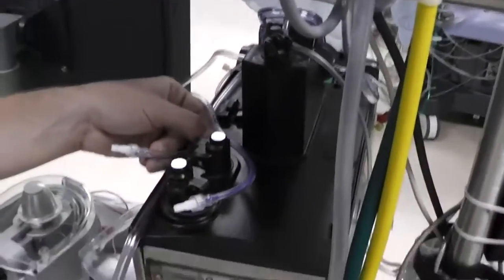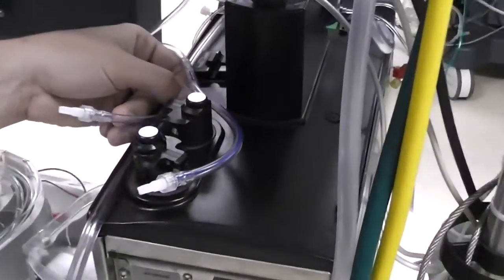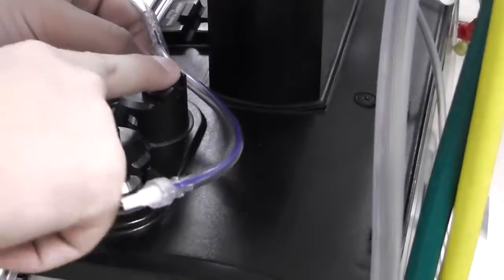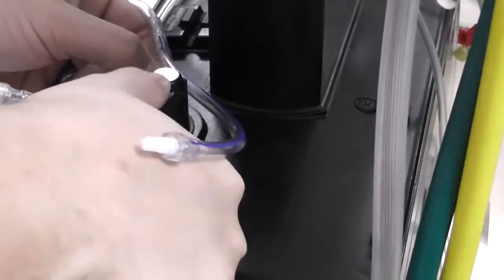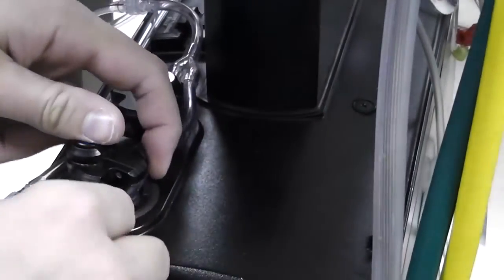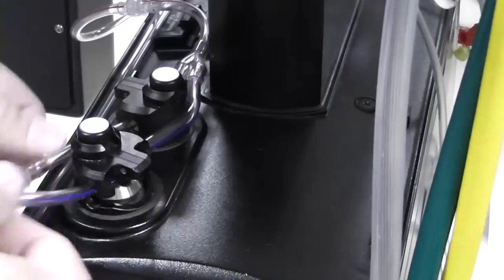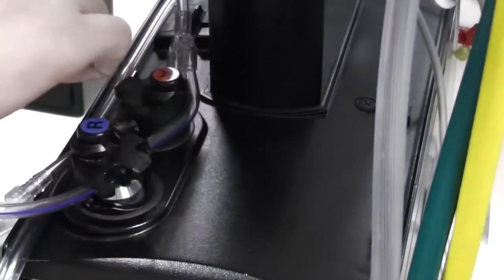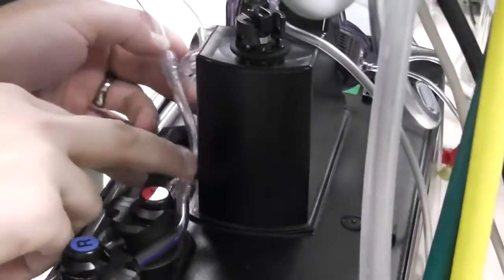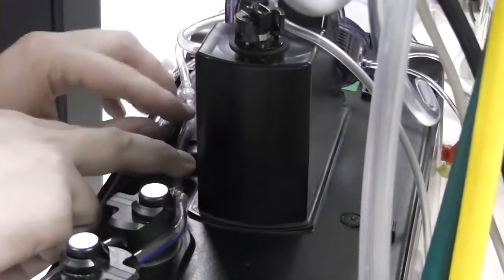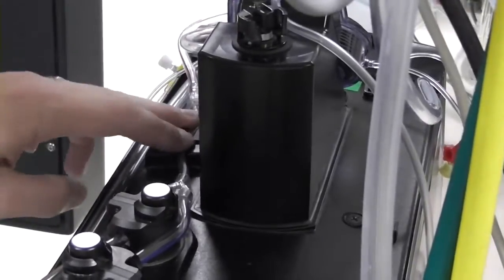Let me see if I can get this in here. You'll see there's these two clamp buttons here. The red one is for antegrade, so we're going to push that down, seat that tubing in there, come around and do the blue, which is retrograde, and then seat this section of tubing with the red line up into this air detector here.